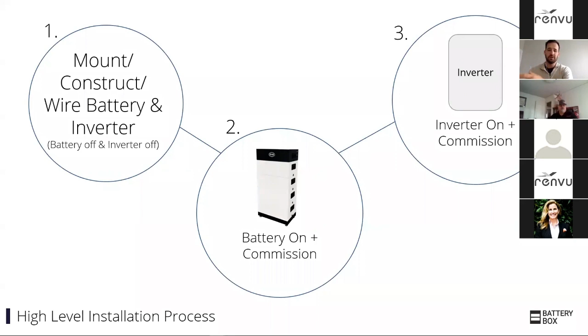So I'm going to drill down to that second step, that battery commissioning. I'll quickly run through this process here. You can see there's a base here at the bottom. You're going to level the base. You're going to stack up the modules, locking them together as you go. I'll get into what that looks like. You're going to put the BCU on the top. You're going to wire it up. You of course have to construct it before you wire it. You're running conduit and whatnot, so the location of those knockouts is critical.